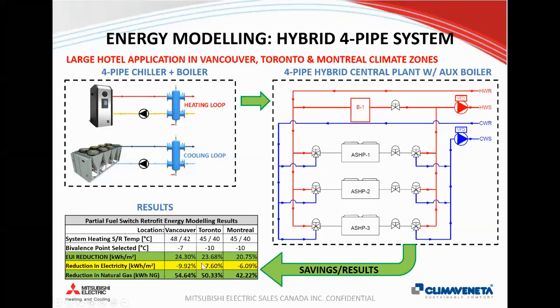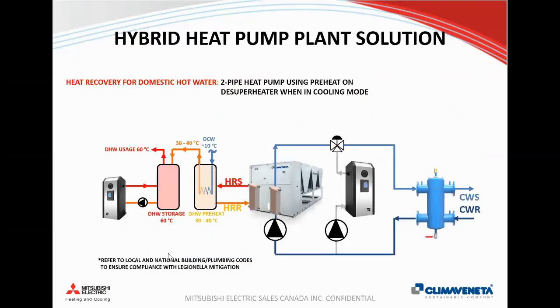But basically, for all 3 climates, even though we have the perception that air-to-water heat pumps need to be the one box that heats at all times, in this example we're only using it down to minus 10. And we actually use them with 3-way valves so that each unit can independently work to the chilled water circuit or to the hot water circuit. What we found was basically a 50% reduction on average for natural gas, a little bit less in Montreal because they have more harsh winters than Toronto does, but still the energy use intensity. And again, this is the metric that will be flowing into the building codes to mandate that the intensity of natural gas itself be reduced. So you can still have significant savings in terms of kilowatt hours by using heat pump systems over natural gas. There's heat recovery available in the units as well.